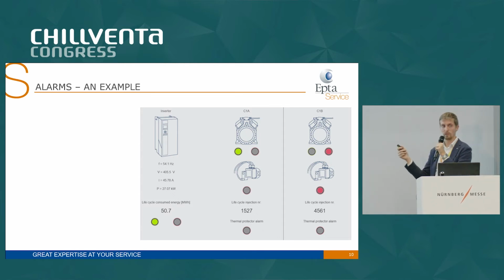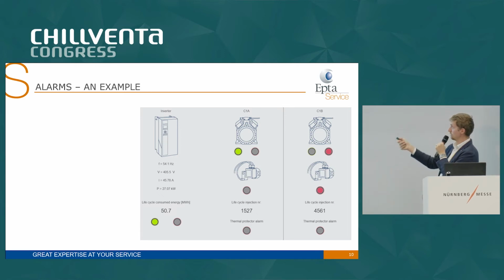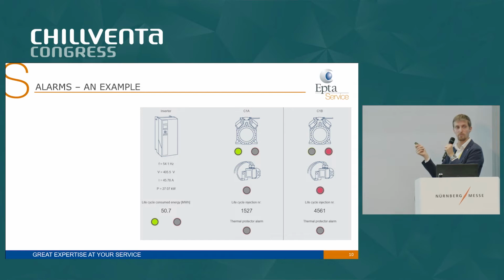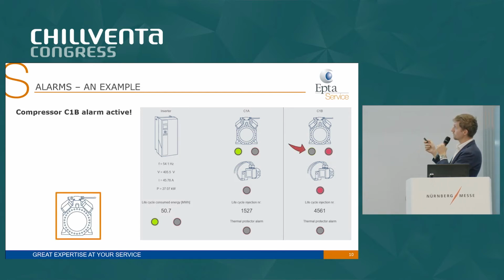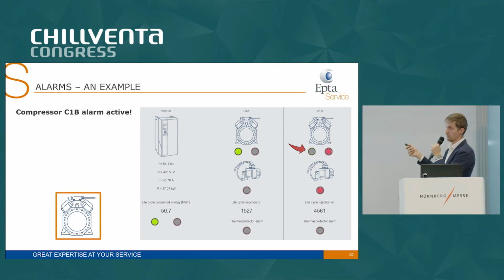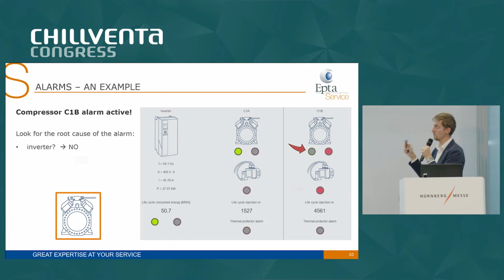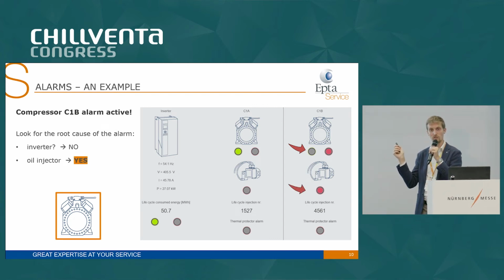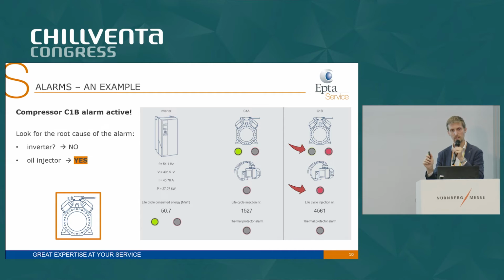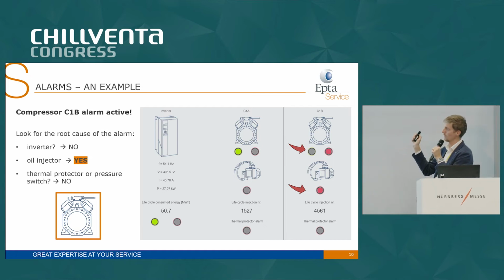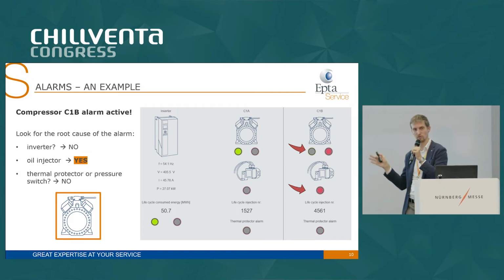I said there is a problem with one of the compressors. Here you see the first one is fine, green lamp, everything is okay. The second one has a red lamp saying that there is a problem with this compressor. And if you visually check here, you will see that there is a red lamp close to the picture of the oil injector. So the problem is not the inverter, it is the oil injector. So it's not only a generic alarm, it's an alarm that is telling you that the problem is related to the oil injector. And of course, the thermal protector lamp is off, so there isn't any problem there.